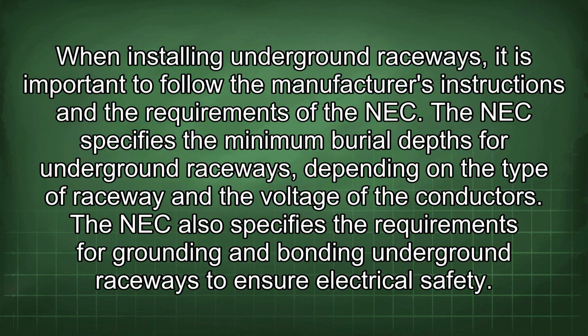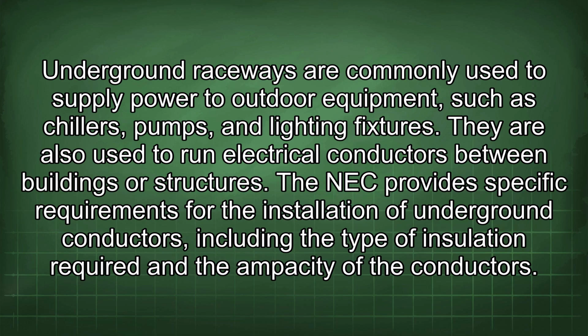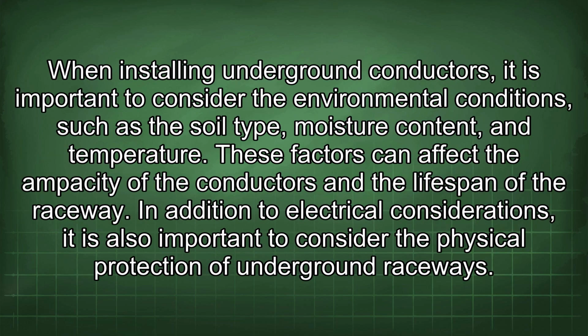When installing underground raceways, it is important to follow the manufacturer's instructions and the requirements of the NEC. The NEC specifies the minimum burial depths for underground raceways depending on the type of raceway and the voltage of the conductors. The NEC also specifies the requirements for grounding and bonding underground raceways to ensure electrical safety. Underground raceways are commonly used to supply power to outdoor equipment, such as chillers, pumps, and lighting fixtures. They are also used to run electrical conductors between buildings or structures. The NEC provides specific requirements for the installation of underground conductors, including the type of insulation required and the ampacity of the conductors. When installing underground conductors, it is important to consider the environmental conditions such as the soil type, moisture content, and temperature. These factors can affect the ampacity of the conductors and the lifespan of the raceway.